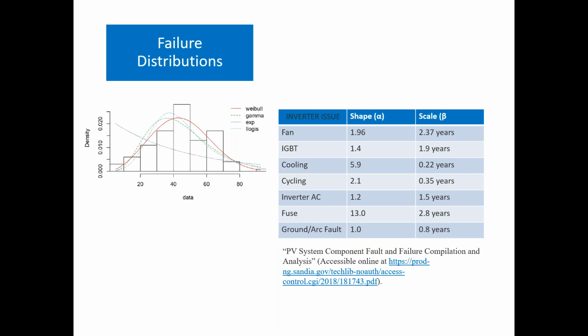So this relates more to central inverters, where you would be working on these individual components: fan, IGBT, cooling, cycling, inverter AC, fuse, and ground and arc fault are the categories of inverter items that were reported in that December 2018 report. And you'll notice that all these beta factors are greater than 1. So that follows up on what Davide was talking about.